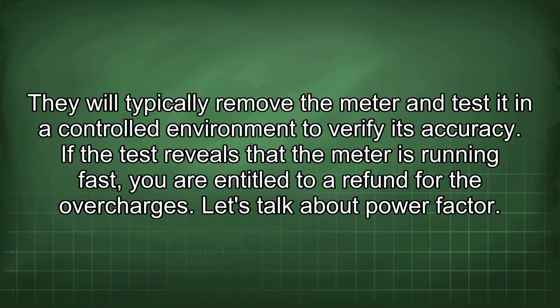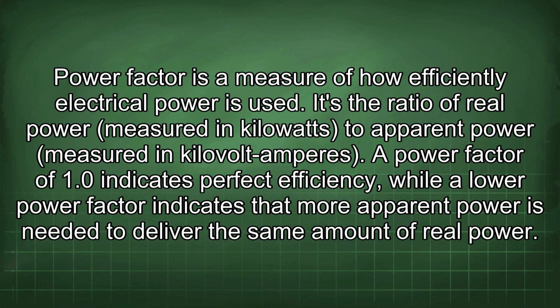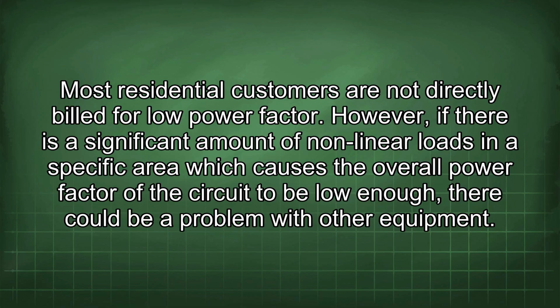Let's talk about power factor. Power factor is a measure of how efficiently electrical power is used. It's the ratio of real power, measured in kilowatts, to apparent power, measured in kilovolt-amperes. A power factor of 1.0 indicates perfect efficiency, while a lower power factor indicates that more apparent power is needed to deliver the same amount of real power. Most residential customers are not directly billed for low power factor. However, if there is a significant amount of nonlinear loads in a specific area which causes the overall power factor of the circuit to be low enough, there could be a problem with other equipment.